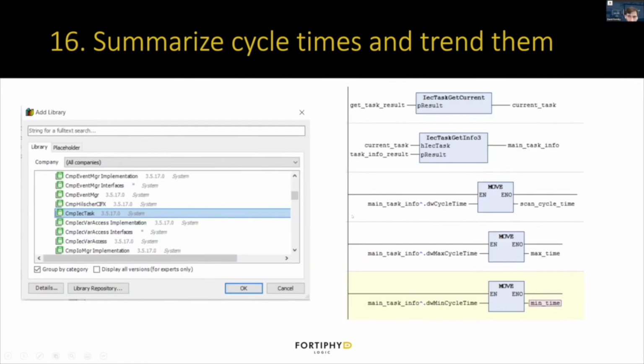For CODESYS, one way to do this is using the CMP IEC task library. You import that library from the library manager. Then you run a few different function blocks to get that information. You get a handle to the current running task, then use the task get info function block on that handle to get information about the task. Some of the things you can get here are the last scan cycle time, the max cycle time, and the min cycle time. You can use those values on the HMI, average them if you want, and trend that to get an idea of the normal behavior of the program.